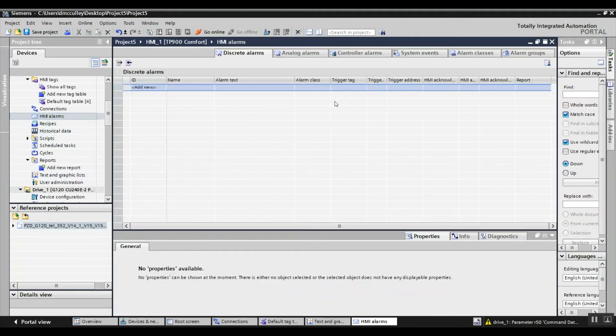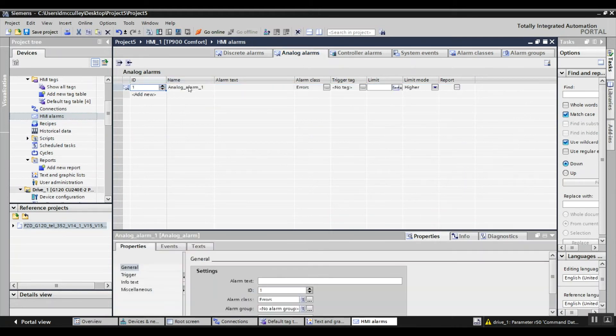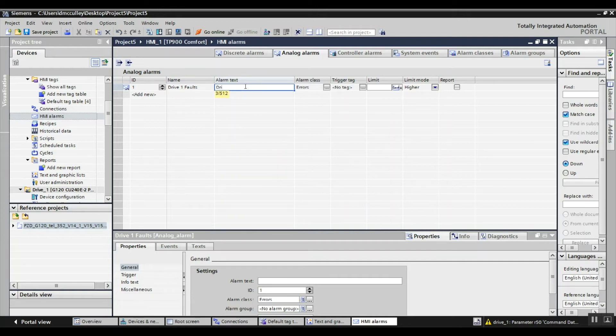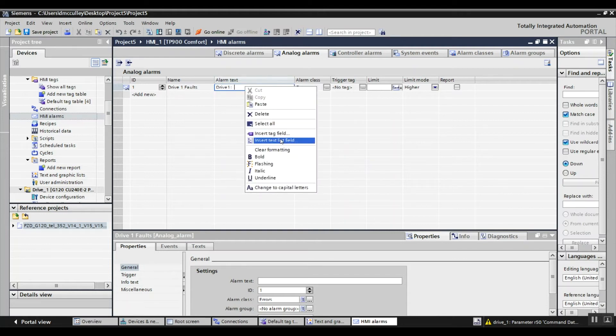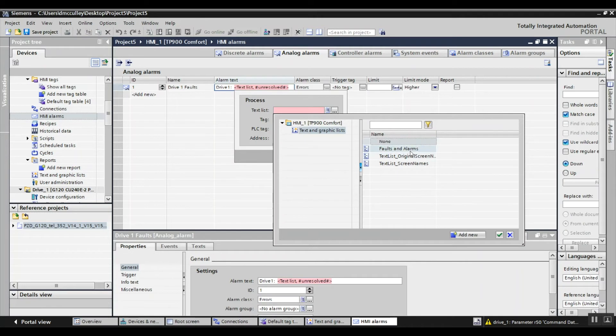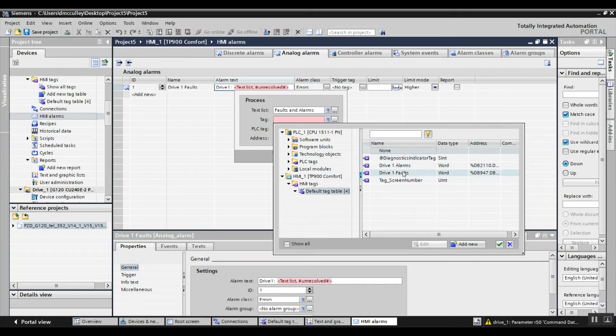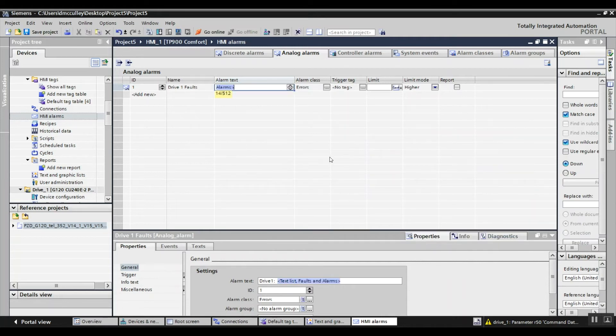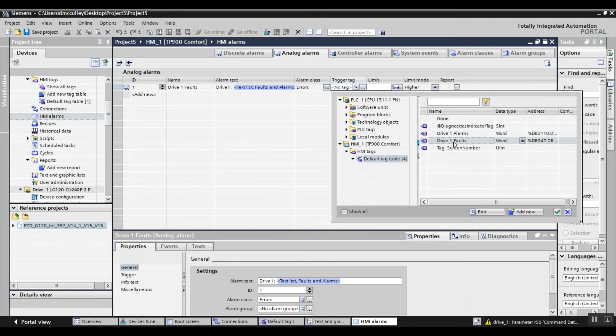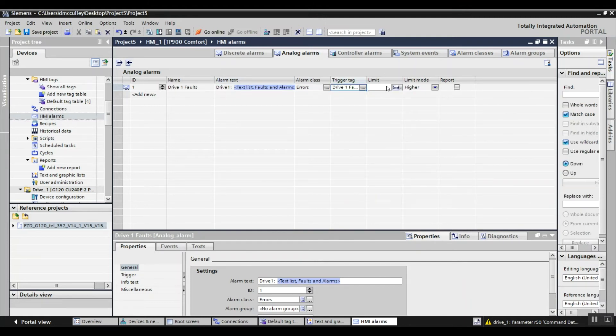Next I need to make it an HMI alarm — it's going to be an analog alarm. Add a new one, call it drive one faults. I want to see this displayed as: drive one semicolon space space, and then insert a text field — basically that text list I created just a second ago — and which fault number is going to display is based upon the drive faults tag. It's an error class, triggered by my drive faults tag, and if the drive faults tag has a value of zero or higher, it'll display.